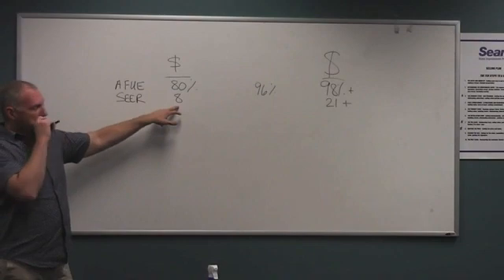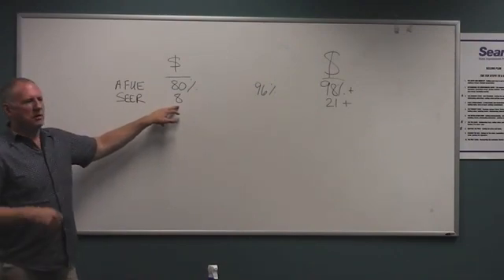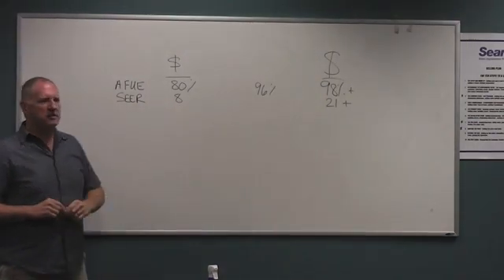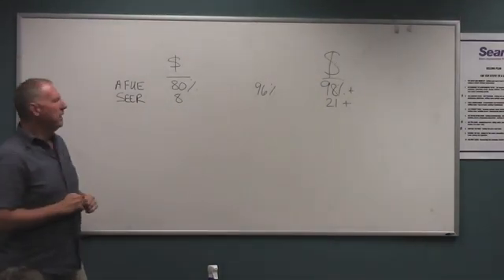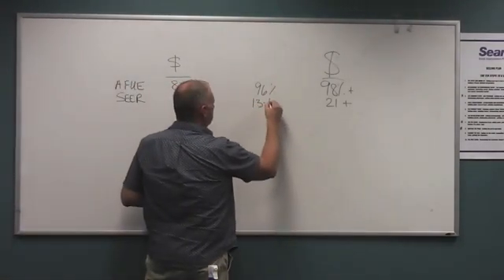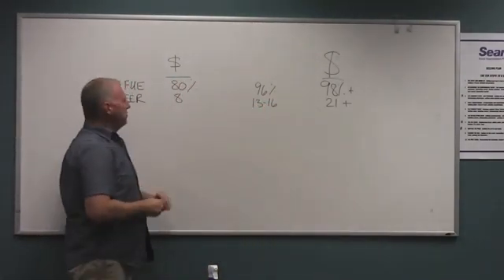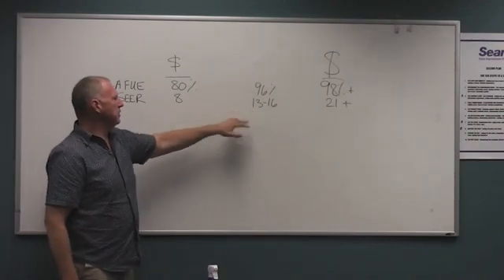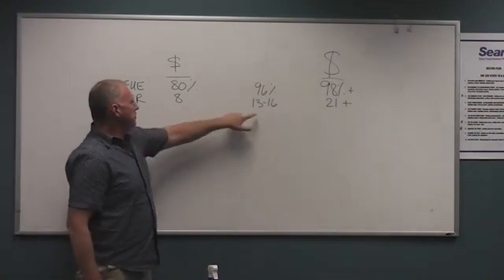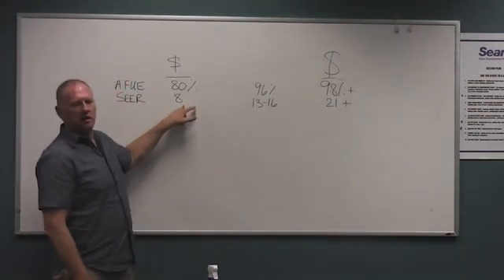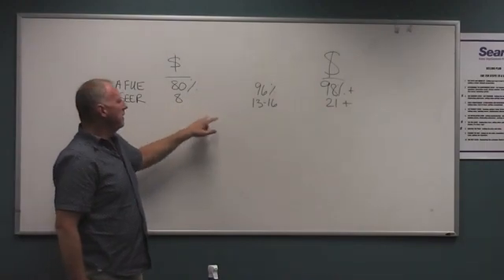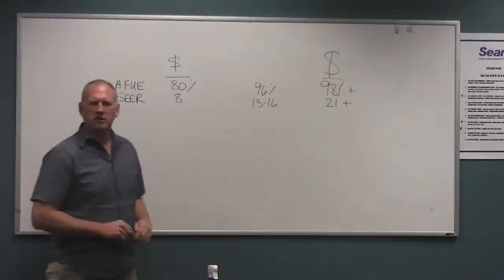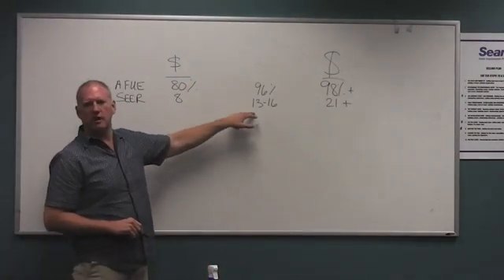On the other side of that, the 8 SEER units, you probably have heard before how air conditioning is very expensive to run. That's because people typically have 8 to 10 SEER units in their home. When you jump up to a 13 to 16 SEER unit, it's very cost effective to run. You're not going to be spending a lot on air conditioning for the home, and you'll be able to operate this for about half the cost as you were an 8 SEER unit. But again, you're not spending the $15,000 that's going to take you up to a 21 SEER unit. So this makes a lot of sense in Utah.